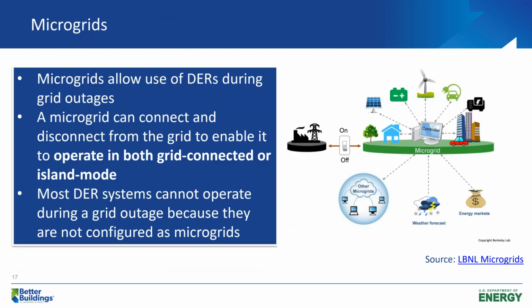So we mentioned microgrids earlier. One common misperception in the industry is that because you have PV and batteries, you can use them when the grid goes down. We talked with vendors who said that's what people think, but it's actually not true—if you're just grid connected, you can't operate the system if the grid's down.